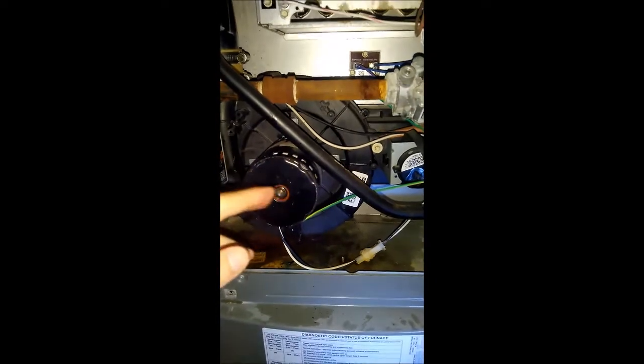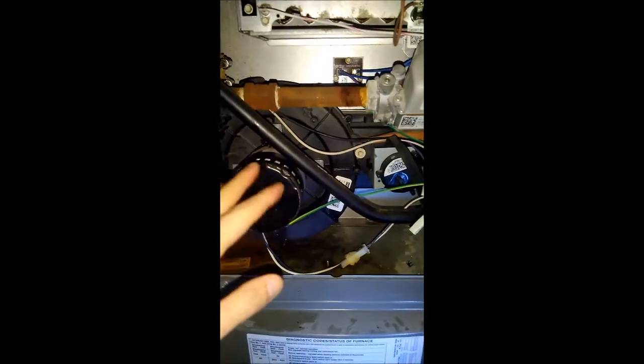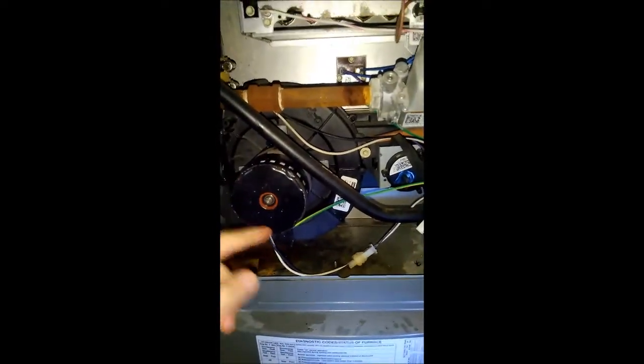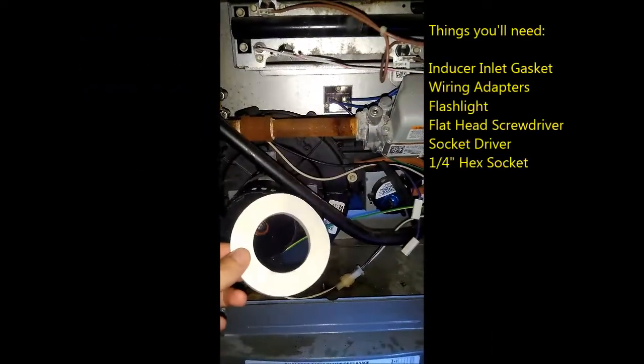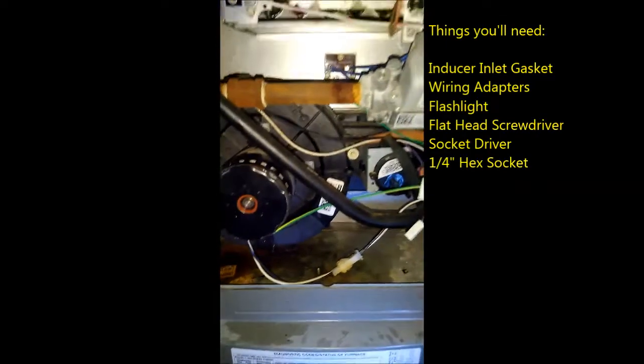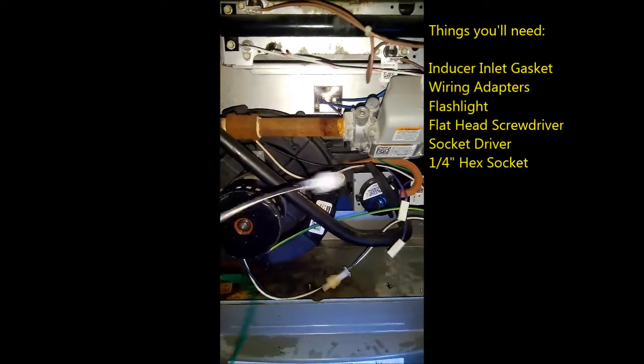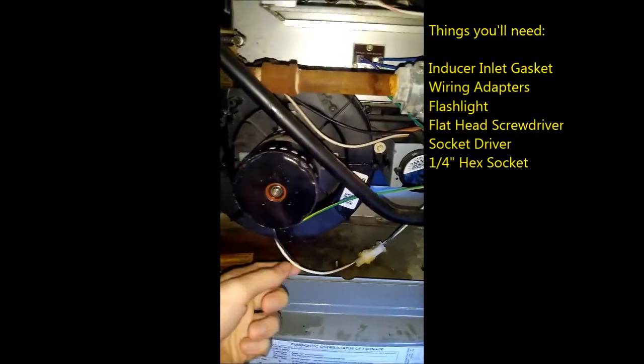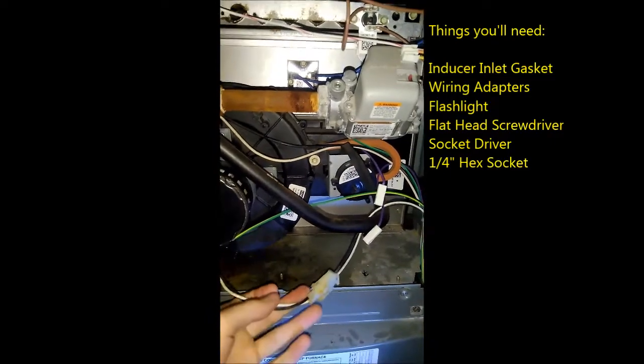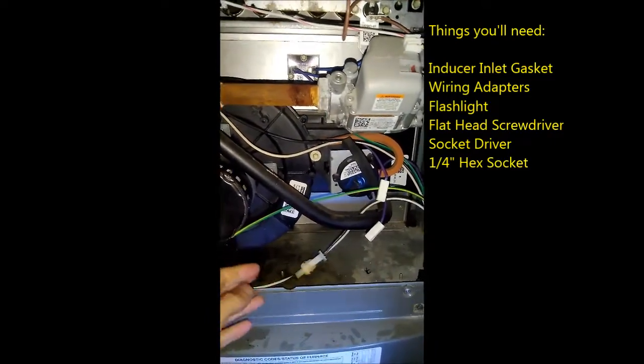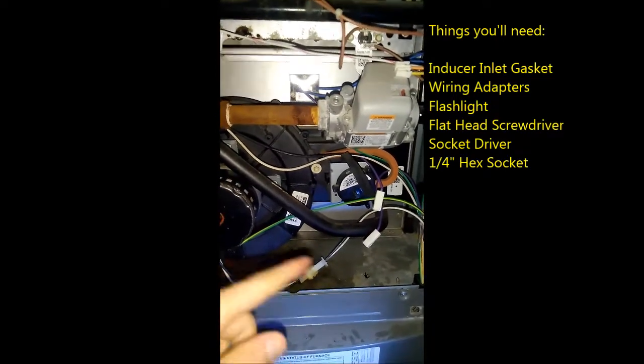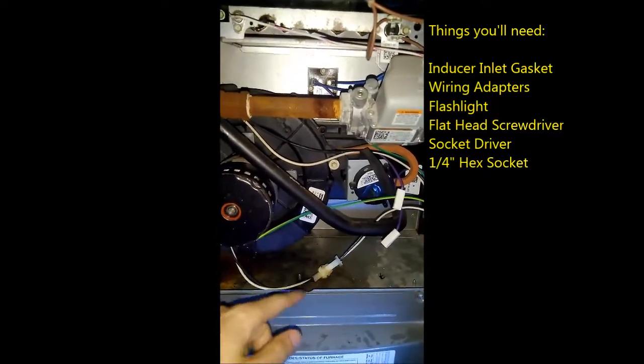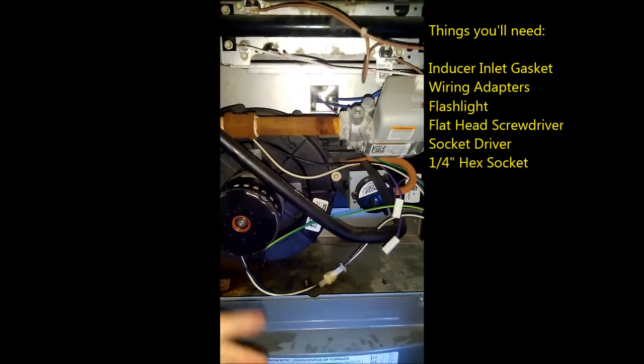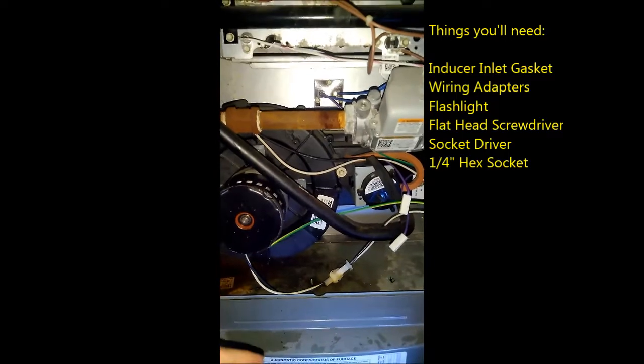As you can see, there's a bunch of stuff in the way. Got to get some stuff out of here first to get access to this thing. There's some screws holding the housing down, and behind there's a gasket. I'm going to show you. This is the stuff you need, right? You've got a brand new gasket. It should come with the new inducer assembly. You might get some wiring harness adapters, which you might need, because the wire that feeds the motor here sometimes has power and then a separate ground wire, and you might need an adapter if it doesn't have a separate ground wire; it'll be part of the harness. So there are usually adapter cables included in your inducer assembly, so check to make sure you've got that.